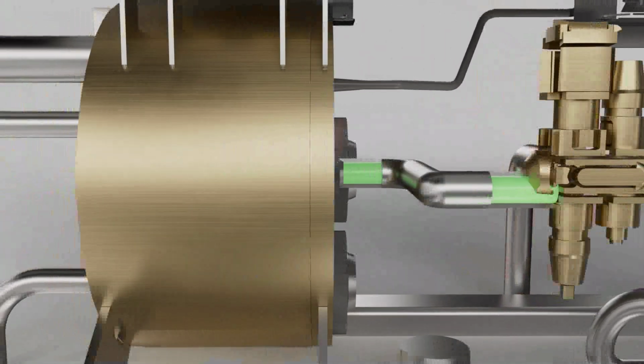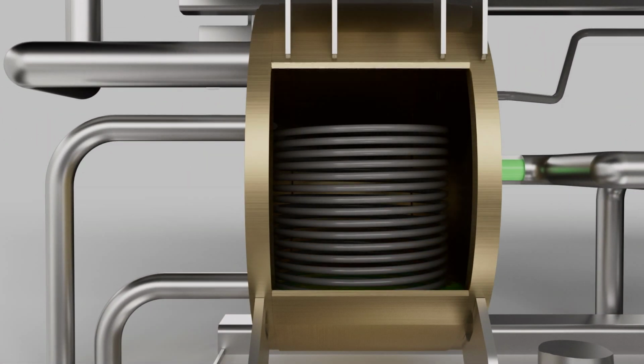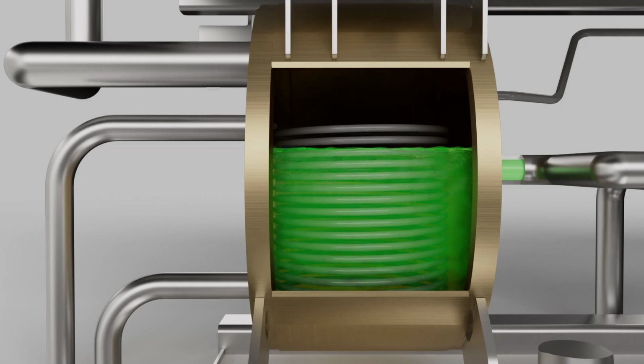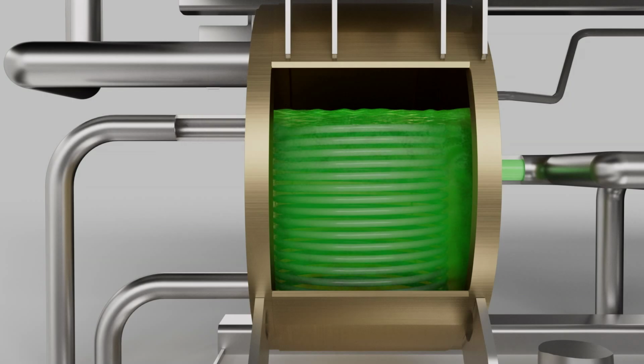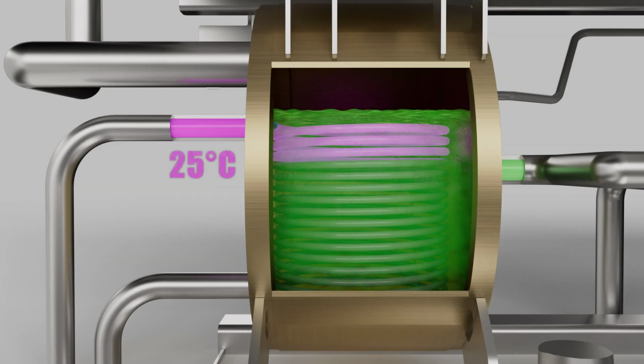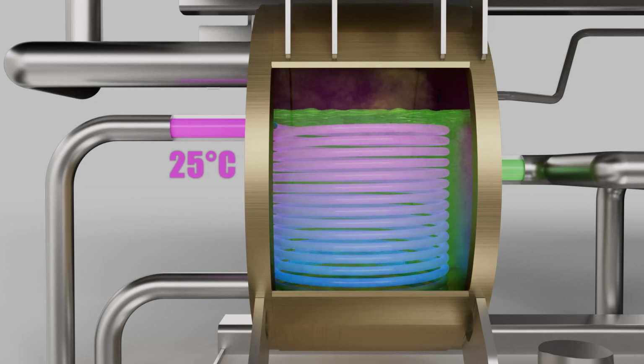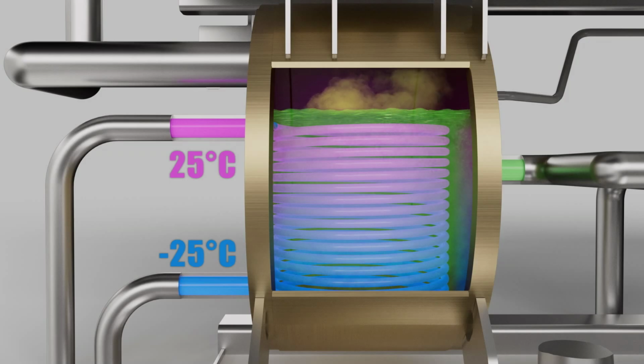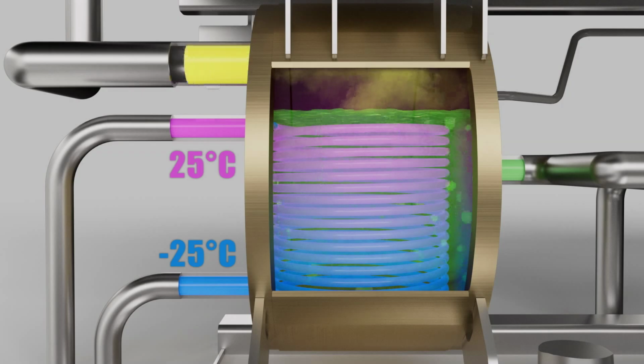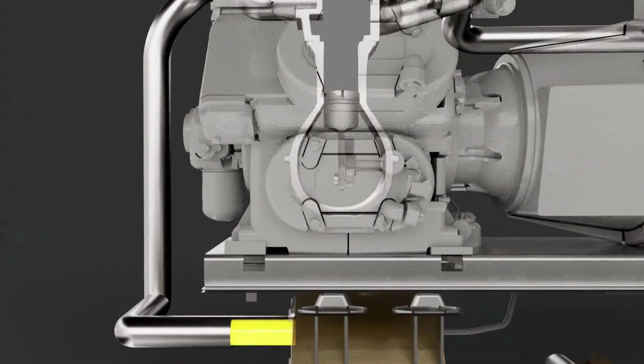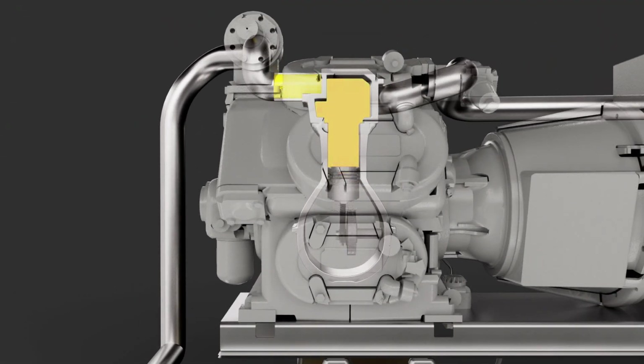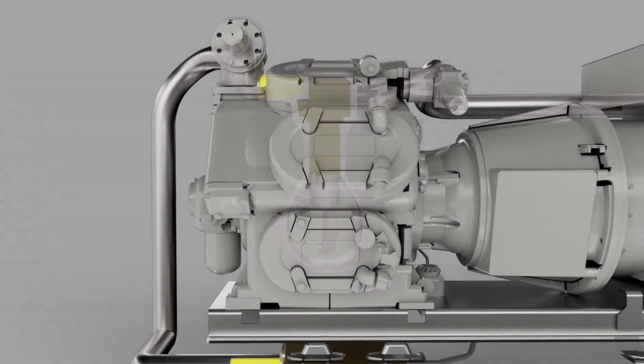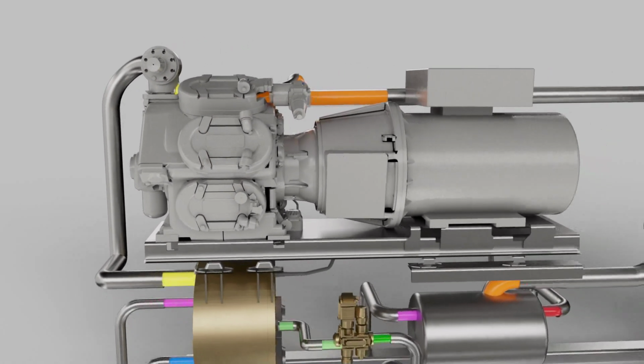The cooled liquid ammonia now flows into an evaporator. The mixture of water and glycol, the brine, which comes from the large water storage tank, also flows through this. The brine flows in at a maximum temperature of 25 degrees Celsius and can be cooled down to minus 25 degrees Celsius by the ammonia. The ammonia absorbs heat from the brine and vaporizes. The ammonia gas now flows to an electrically driven compressor. By compressing the gas, the temperature increases once again. The hot gas flows back to the condenser, and the cycle starts all over again.